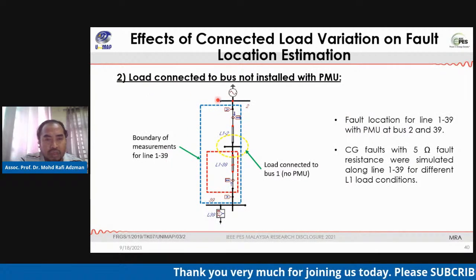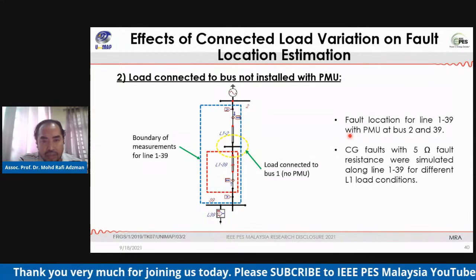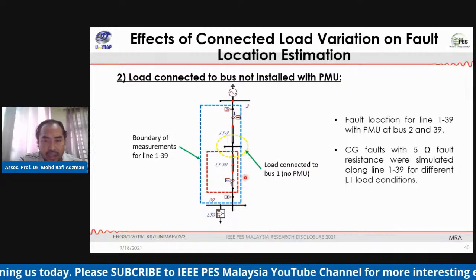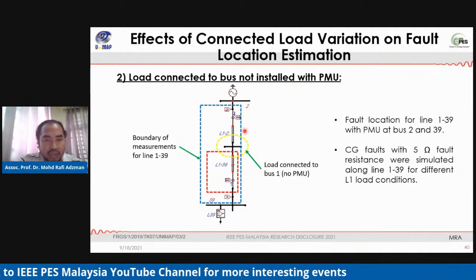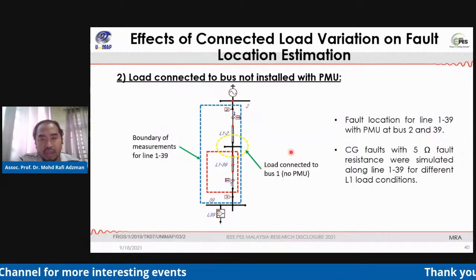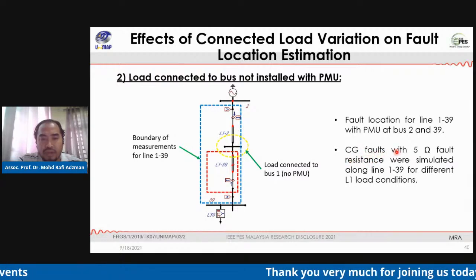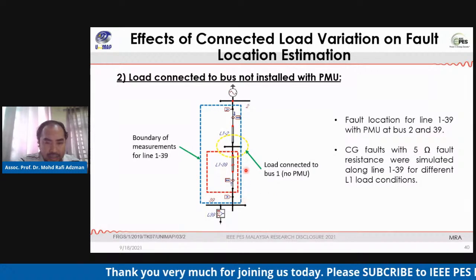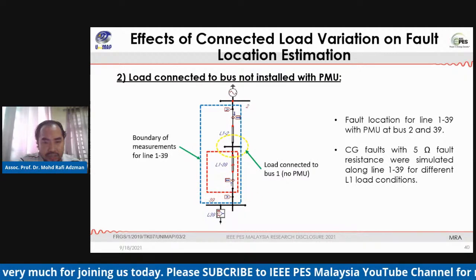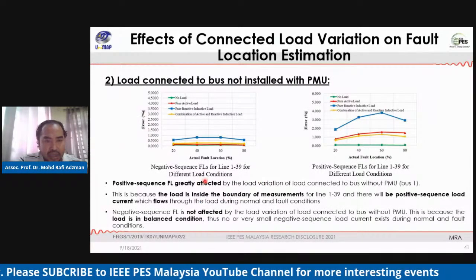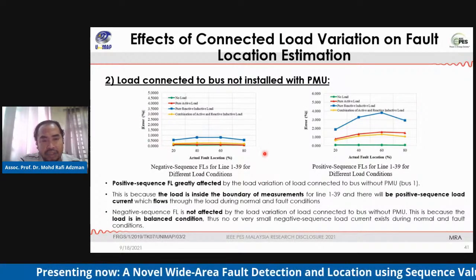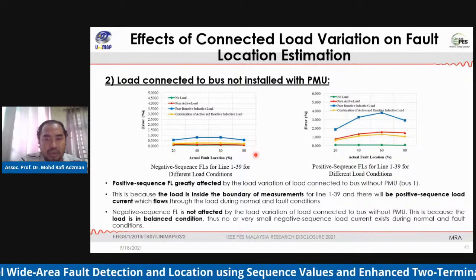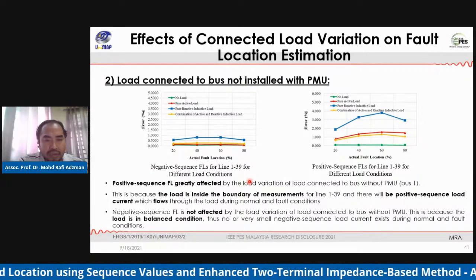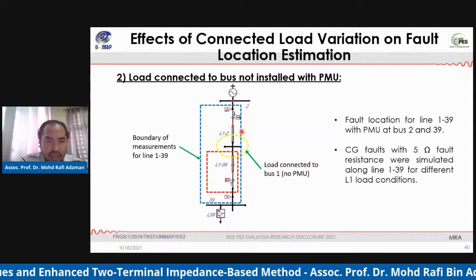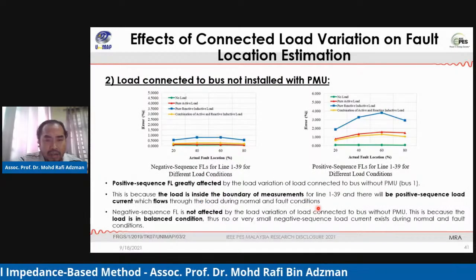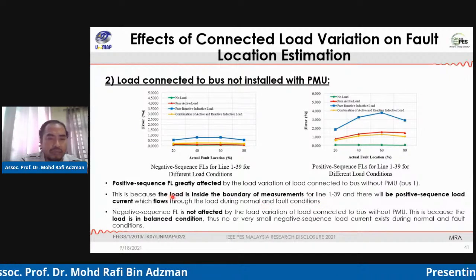For the second case, the load is connected to a bus which does not have a PMU installed. So here we have the fault location for line 1 to 39, with PMU at bus 2 and bus 39. The C to ground fault with 5 ohms fault resistance was simulated along line 1 to 39 for different load conditions. We can see from the result that the positive sequence fault location is greatly affected by load variations, with the load connected to a bus without a PMU.